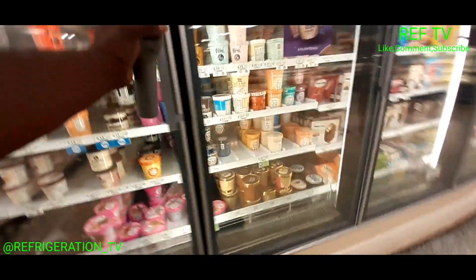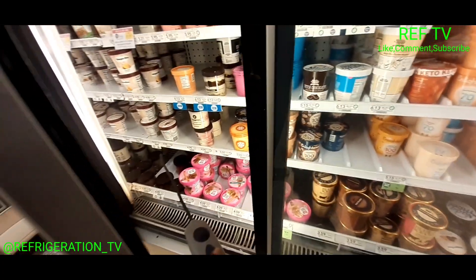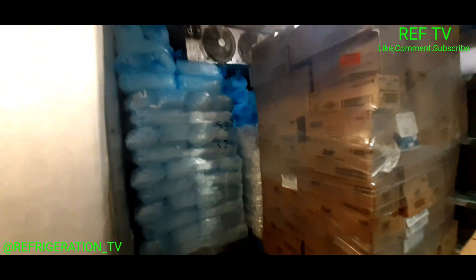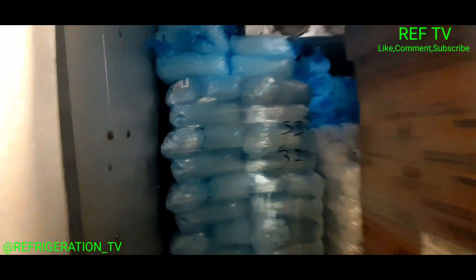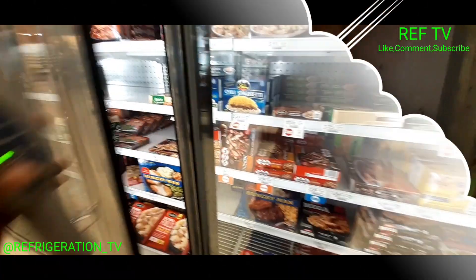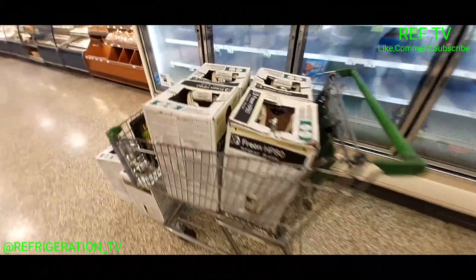Normally when you walk the store you just stick the detector right in here — this thing was screaming, but there's refrigerant in here. Let's head to the walk-in cooler and hit a couple cases and go from there. Small traces, nothing big. This is a low-temp freezer grocery case — also on rack two. They got a whole bunch of ice. Looks like they're stocked up for coronavirus. Plenty of waffles and frozen food — well covered.